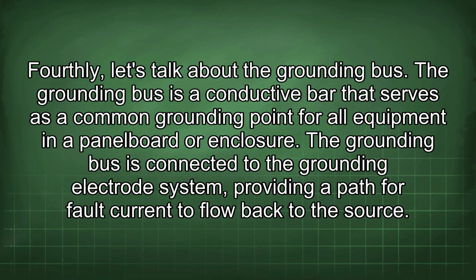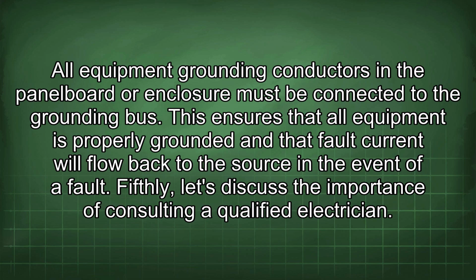Fourthly, let's talk about the grounding bus. The grounding bus is a conductive bar that serves as a common grounding point for all equipment in a panel board or enclosure. The grounding bus is connected to the grounding electrode system, providing a path for fault current to flow back to the source. All equipment grounding conductors in the panel board or enclosure must be connected to the grounding bus.